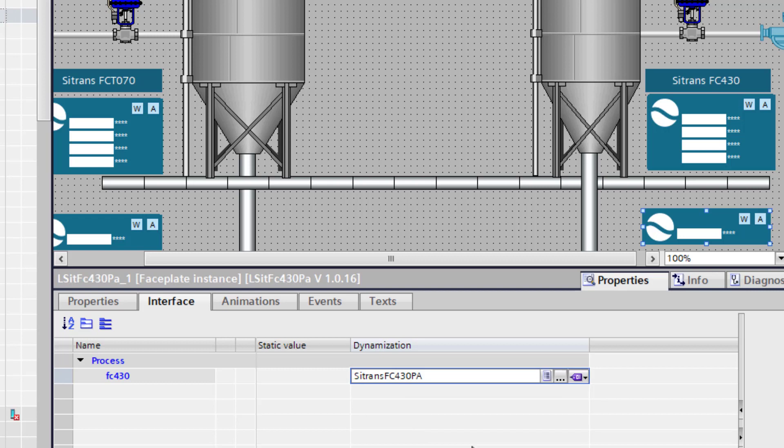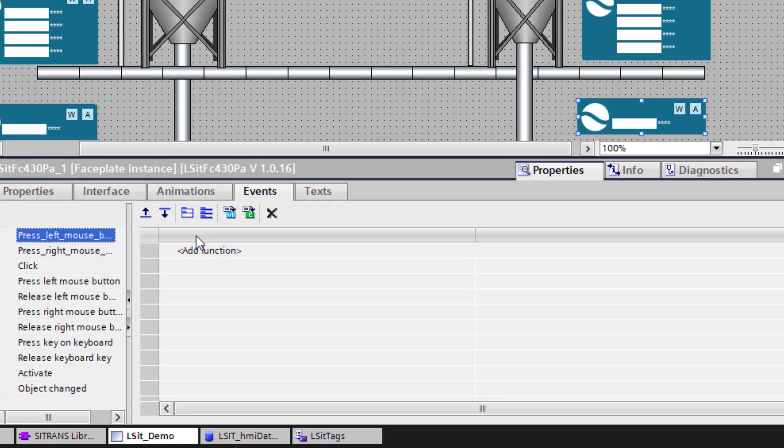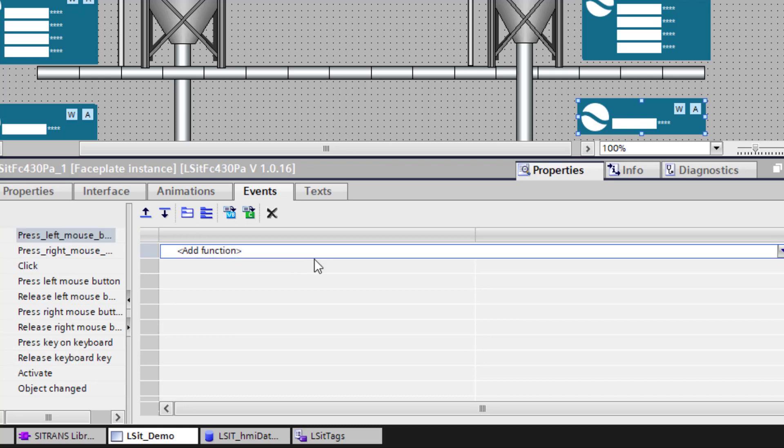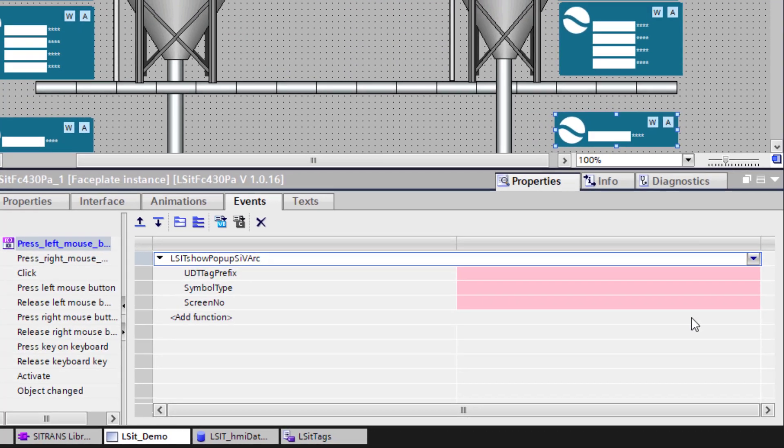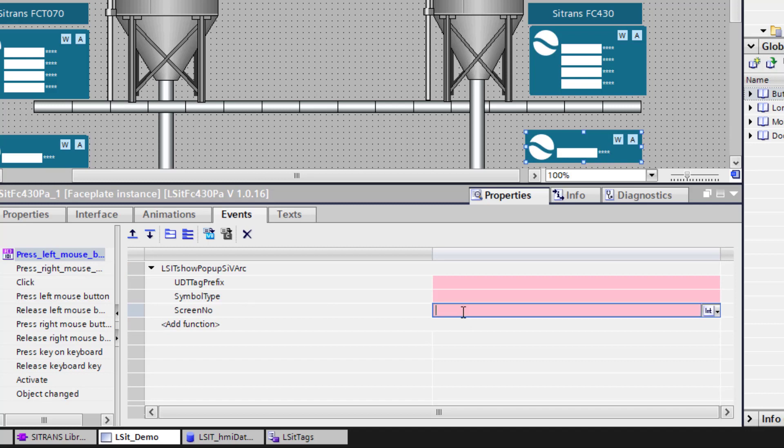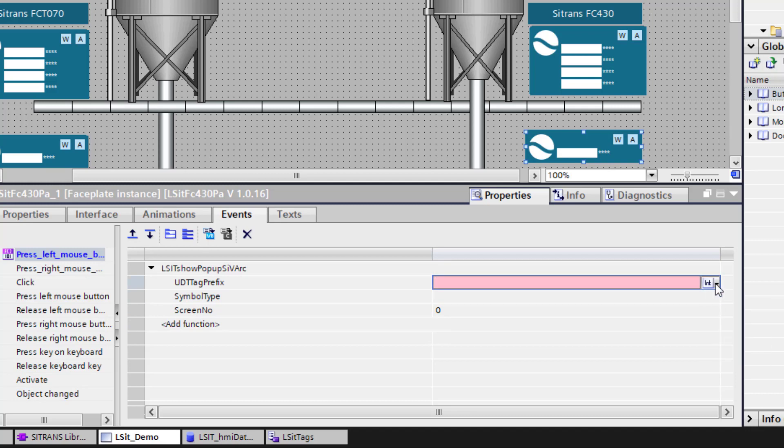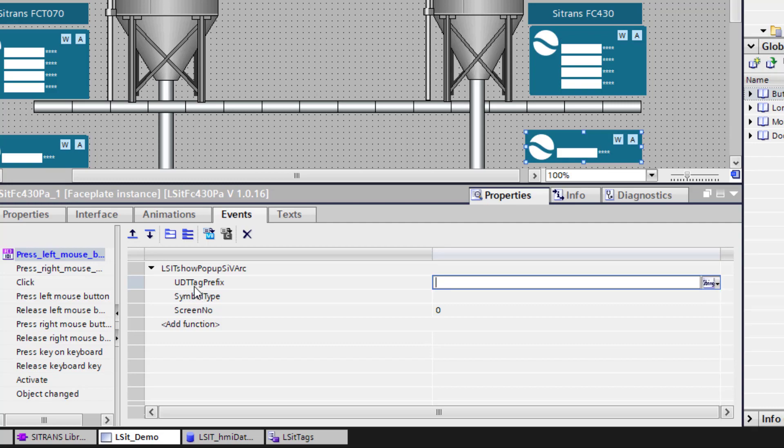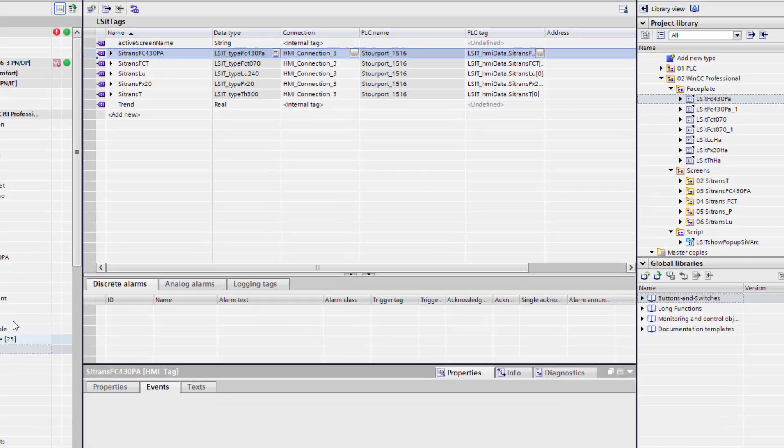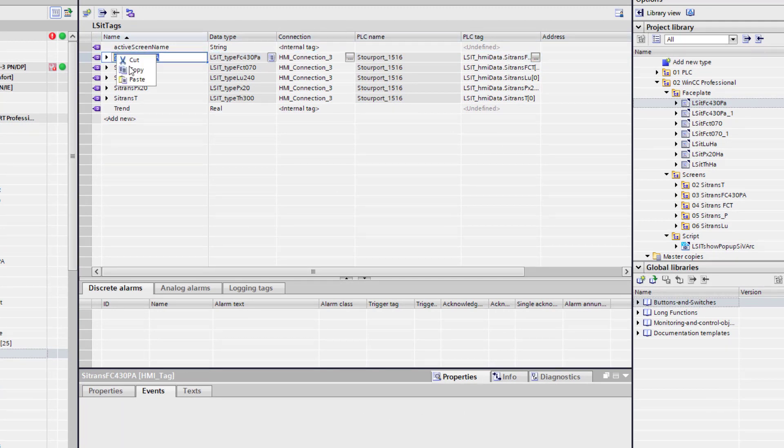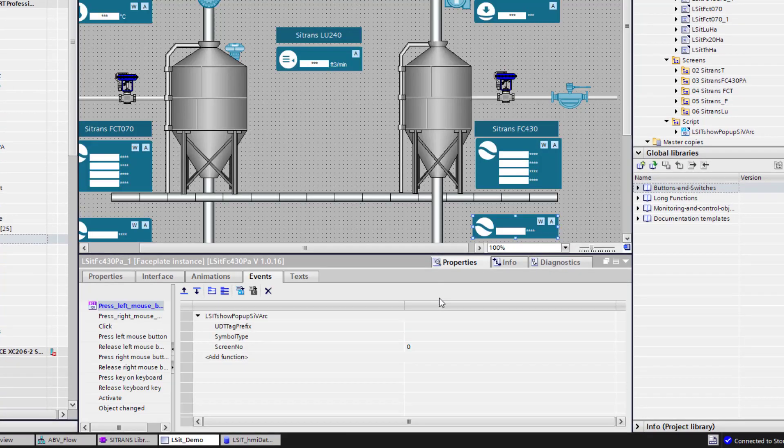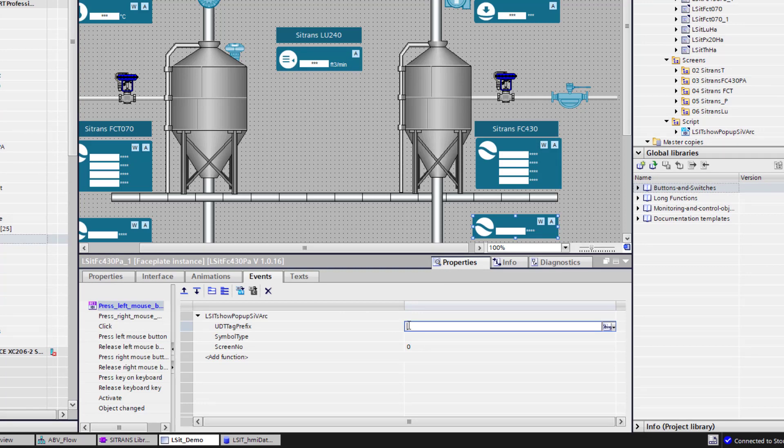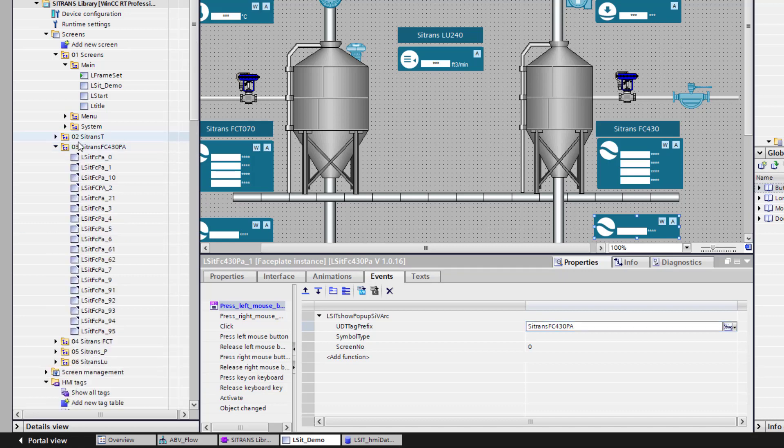And now I just need to launch the visual basic code. That's sitting in the back. So I go to my events. And then on the left mouse button click. I select the visual basic code. And then I get these three functions. Well the screen number. I always want to start with screen zero. And then these two values. Are strings. So you need to change those to strings. So the UDT tag prefix. Comes from your. LSit tags table. So if I open this up. It's this value here.